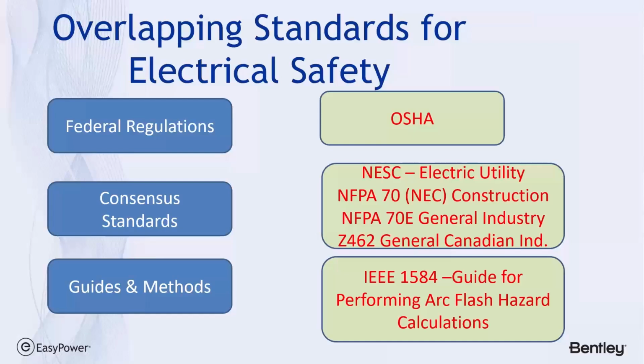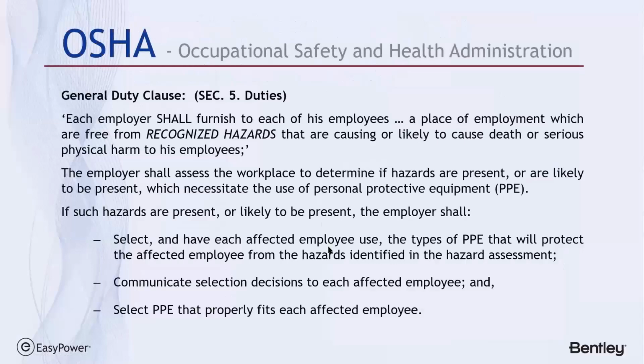And then finally, there are guides and methods to actually do the calculations. We'll be focusing on IEEE 1584, although there are other methods, and part of the requirement is to document which methodology is being used for developing a safety program. I mentioned the general duty clause. Basically, it says employers must provide a place of employment which is free from recognized hazards. So much of this first hour is focused on making sure that everyone understands arc flash has been recognized as a safety hazard in the industry.